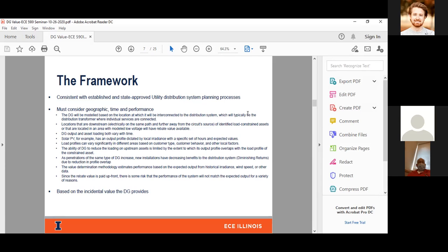A key concept here when we're talking about penetration of DG and its value to the grid is that as penetration of the same type of DG increases, there's the concept of diminishing return, where you see decreasing benefit to the distribution system, because the output profile of that specific DG type no longer overlaps with the asset that you're trying to evaluate. That's where the concept of diminishing return comes in, and that's an important one to keep in mind.